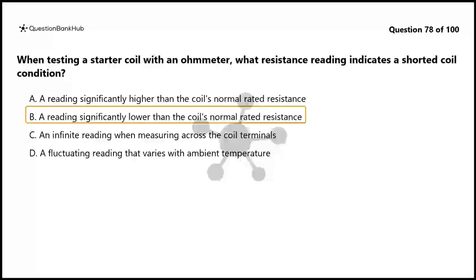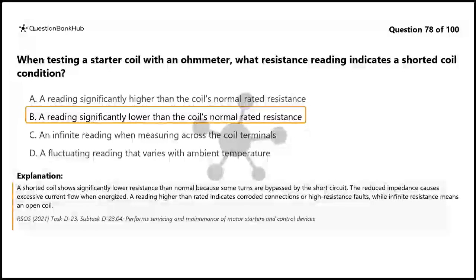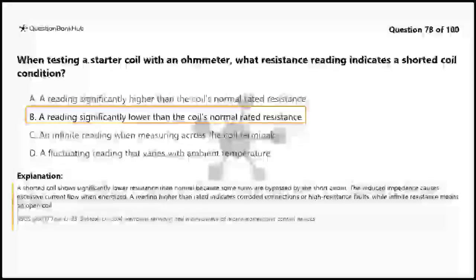The correct answer is B. A reading significantly lower than the coil's normal rated resistance. A shorted coil shows significantly lower resistance than normal because some turns are bypassed by the short circuit. The reduced impedance causes excessive current flow when energized. A reading higher than rated indicates corroded connections or high resistance faults, while infinite resistance means an open coil.